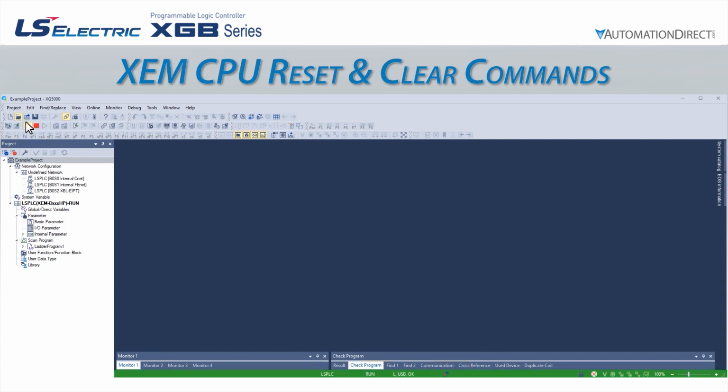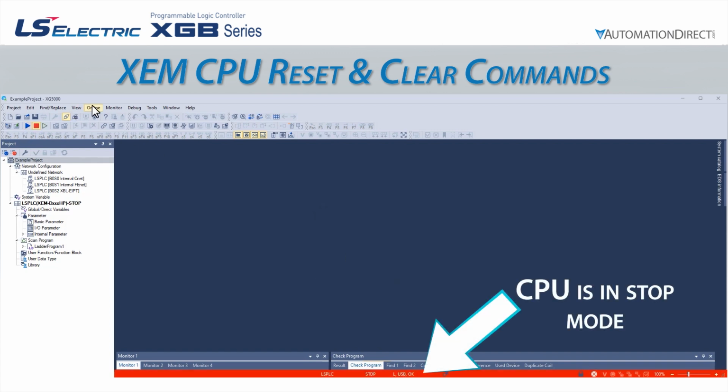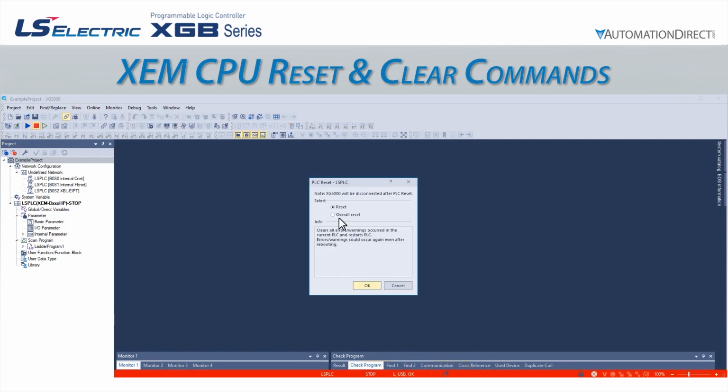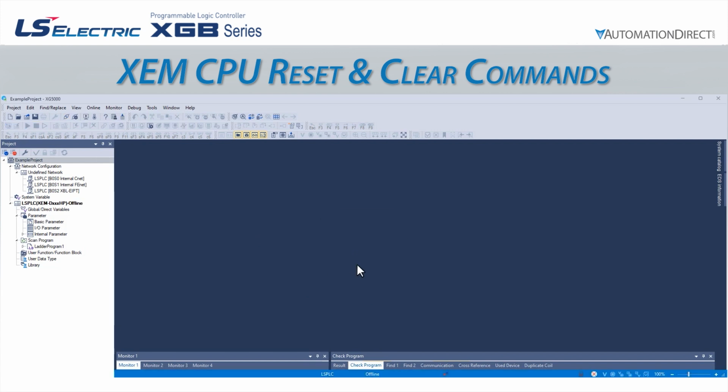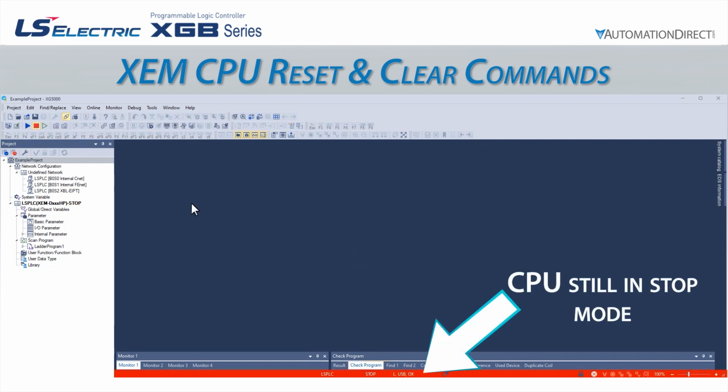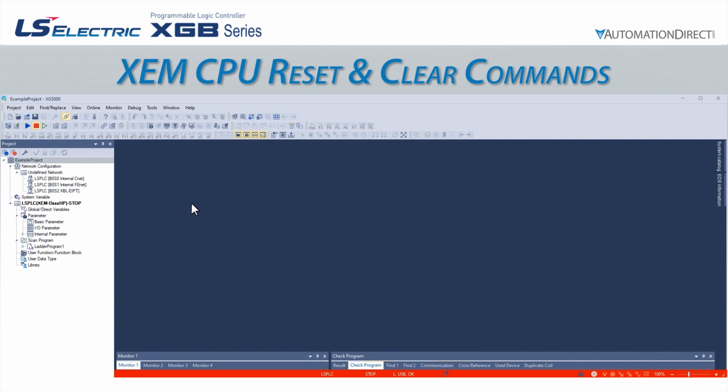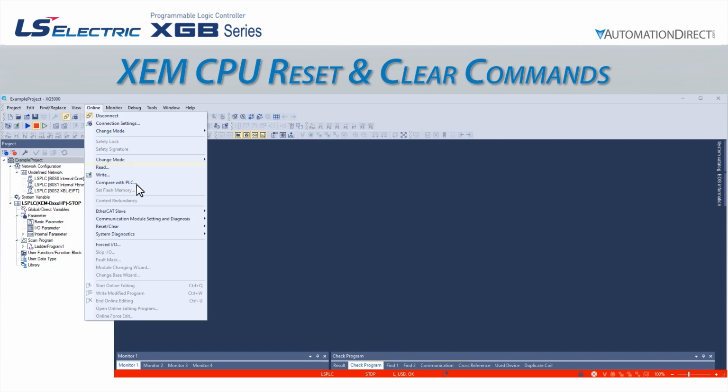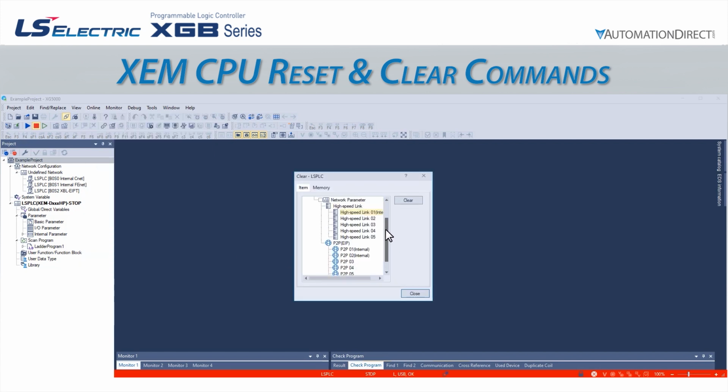Both these commands may be done in stop or run mode, but the CPU mode switch must be in the stop position. Once the PLC reboots, it will stay in the same mode it was in when the reset was requested. If we want to select the clear PLC command, we must be online and the PLC must be in stop mode. Selecting Clear PLC will open the Clear LSPLC pop-up window.